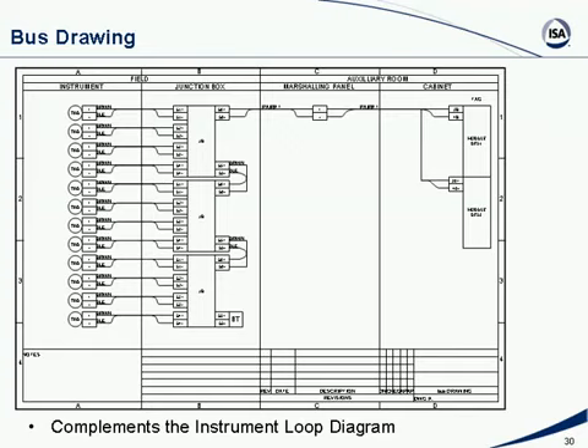Another important fact is that one segment drawing can now replace up to 16 instrument loop diagrams, reducing not only the hardware and wires associated with Fieldbus, plus the cable trays and ladders, but also the amount of drawings and engineering work. That's another CapEx, or capital expenditure, reduction that comes out of Fieldbus.